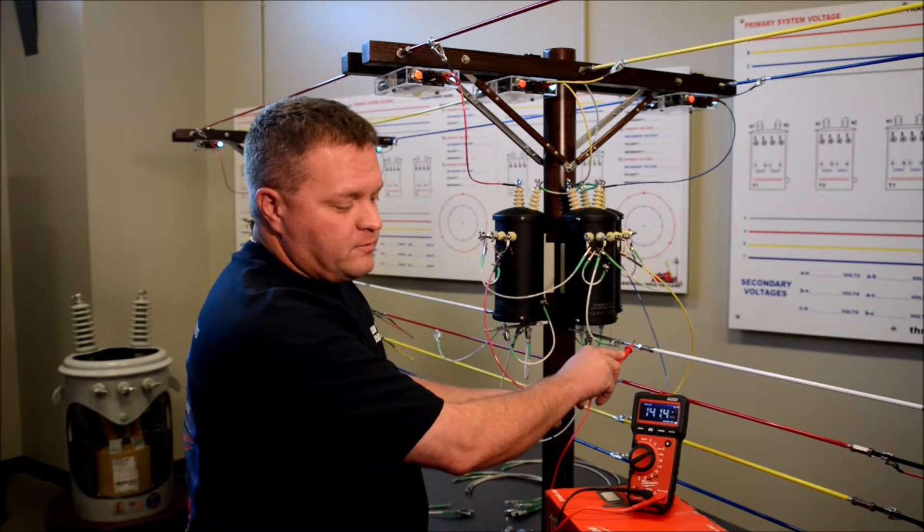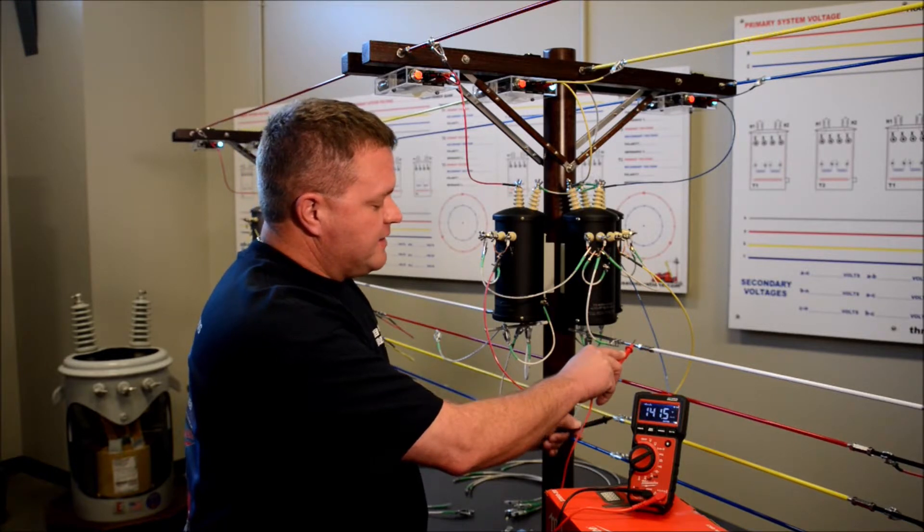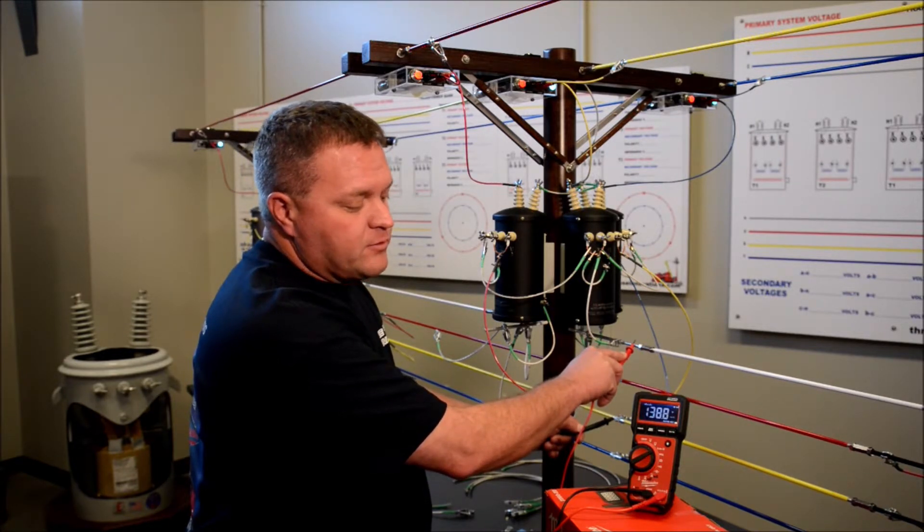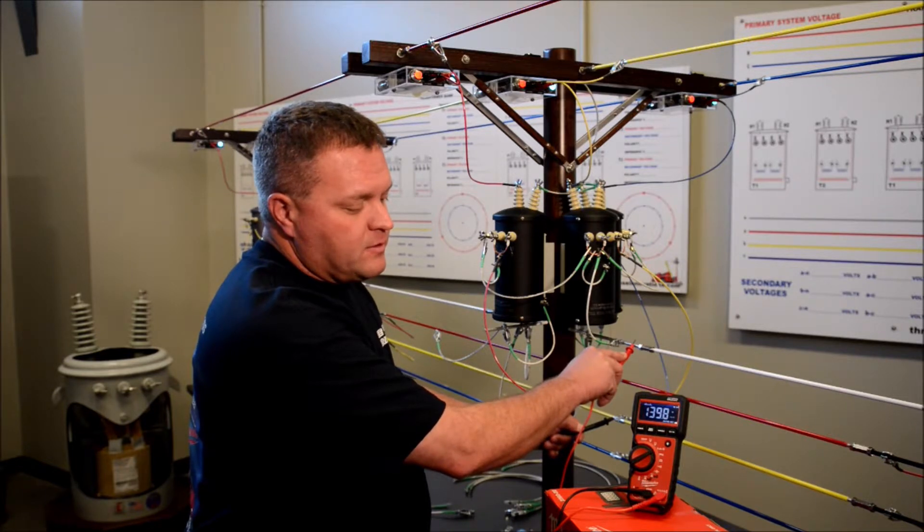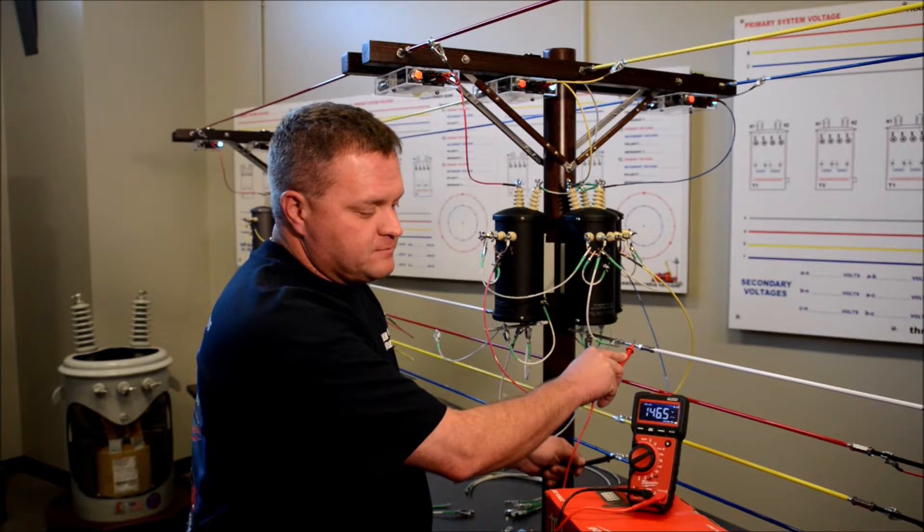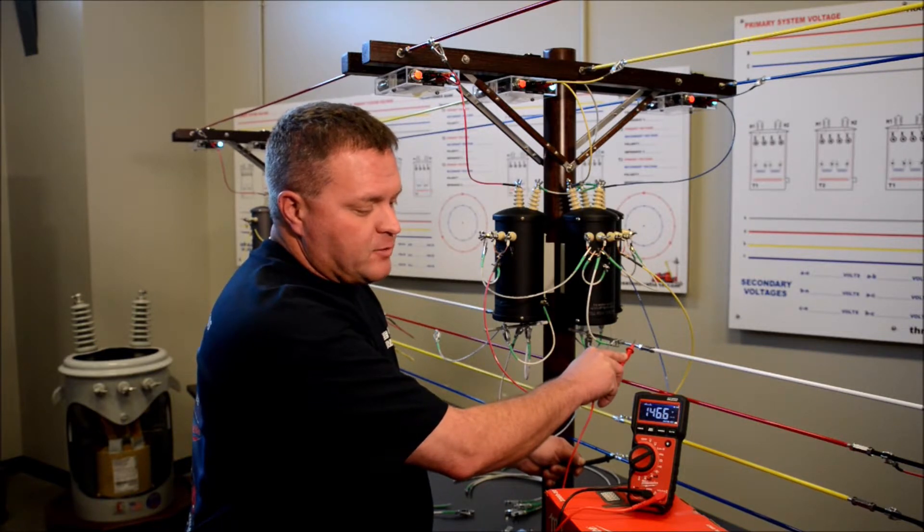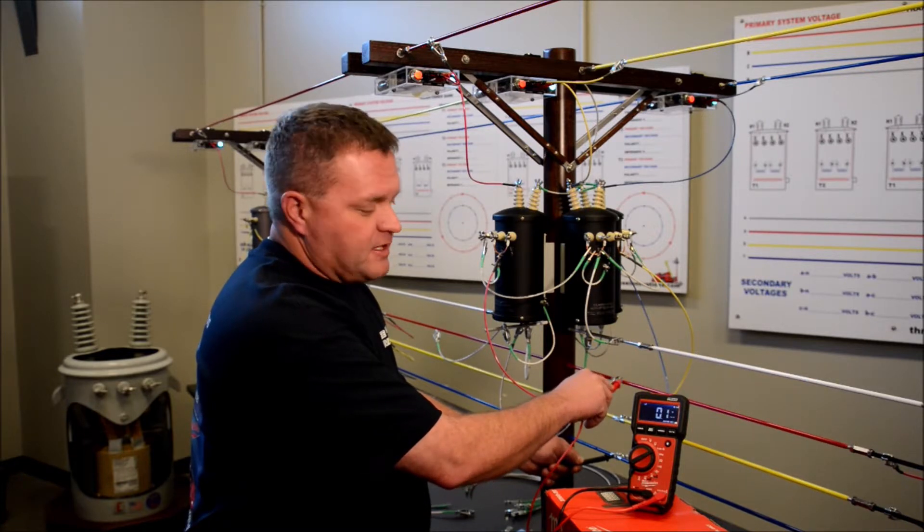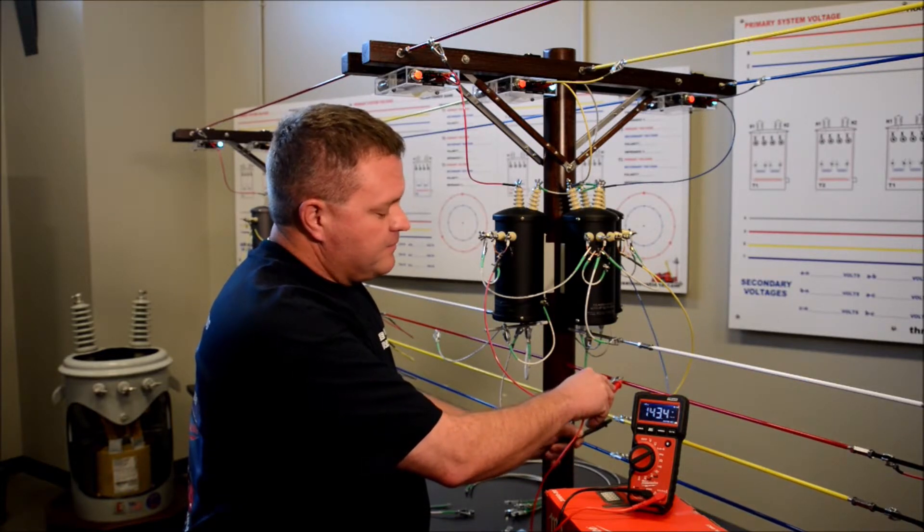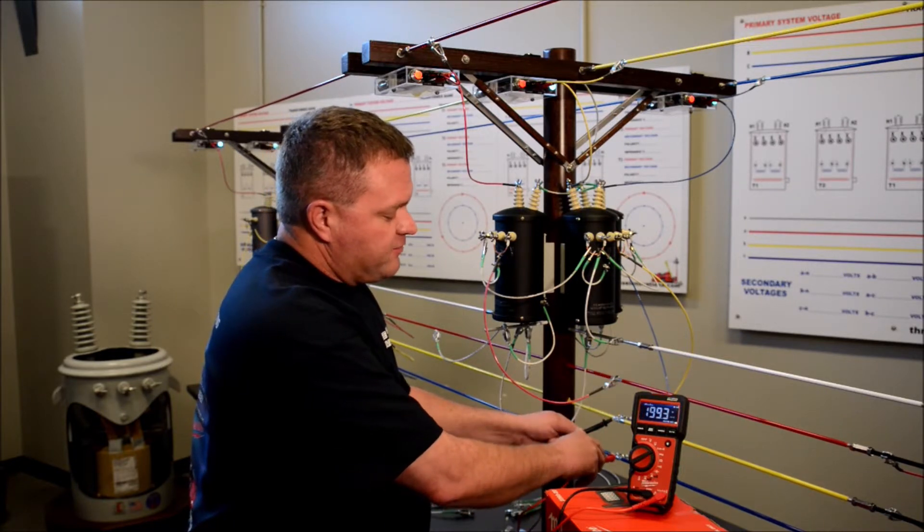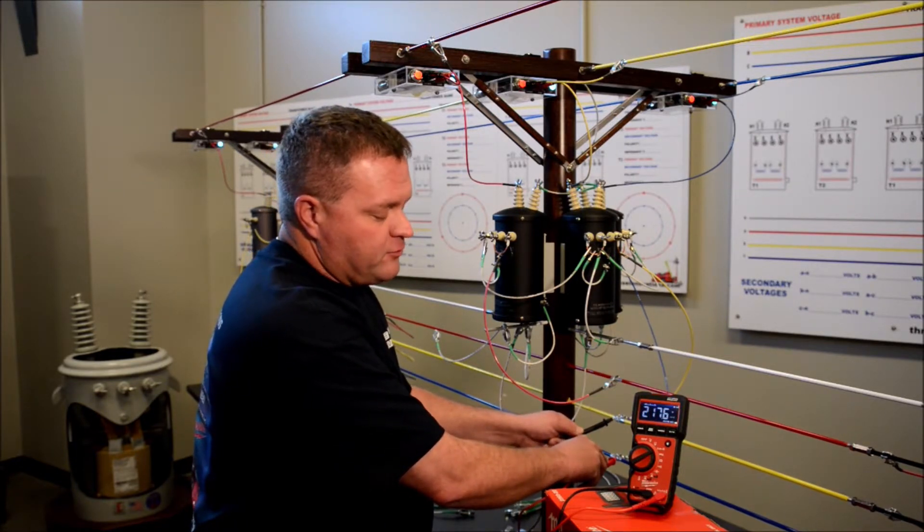So 141.4 for A, B - 137, 138, we're climbing on up there - 140. And C phase, a little bit higher, we got 146. Now we're going to go phase to phase. A to C, 214. A to B, 217. B to C, 217.